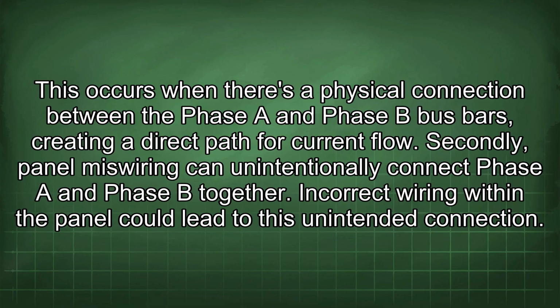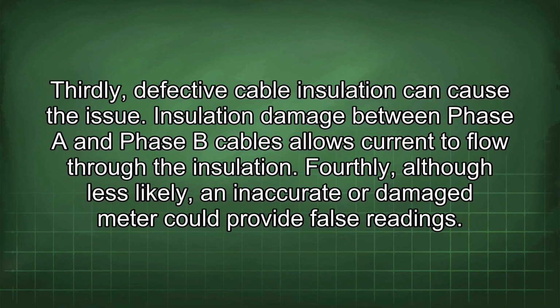This occurs when there is a physical connection between the phase A and phase B bus bars, creating a direct path for current flow. Secondly, panel miswiring can unintentionally connect phase A and phase B together. Incorrect wiring within the panel could lead to this unintended connection. Thirdly, defective cable insulation can cause the issue. Insulation damage between phase A and phase B cables allows current to flow through the insulation.